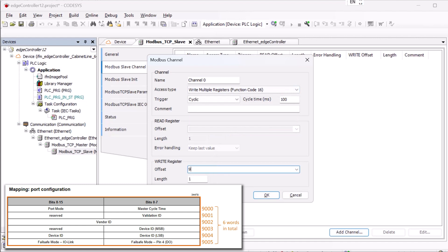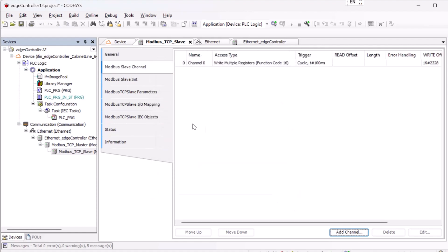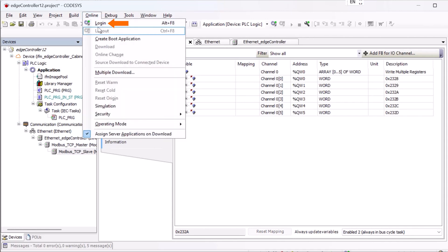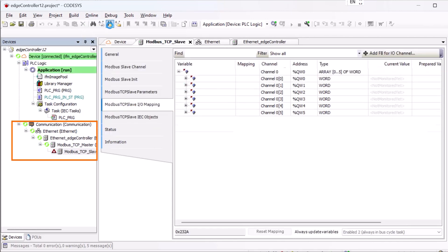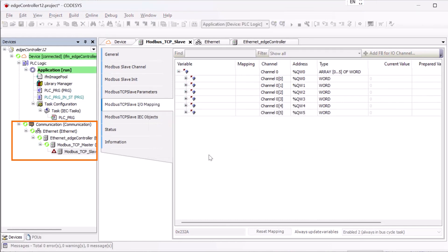Back to the configuration of our new Modbus channel. We now select Register 9000 with a total length of 6 words as address for the write process. Before we start parameterizing the port in the IO-Mapping, we log in and check that the settings are OK. Green circles appear on the left side, which means that everything is OK and we can continue.